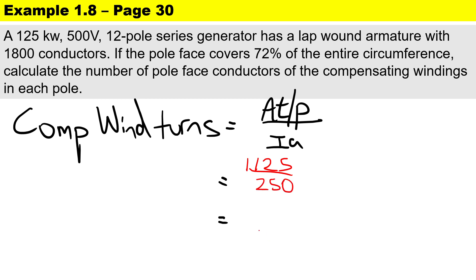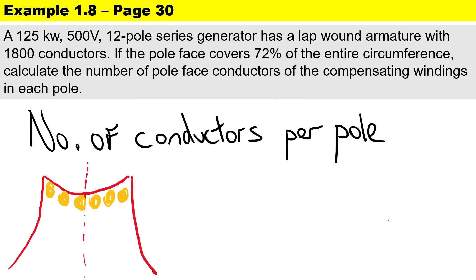The last step is to work out the number of conductors per pole. We take the compensating winding turns per pole of 4.5 and multiply by the two sides of the pole face. Therefore there are nine conductors per pole.